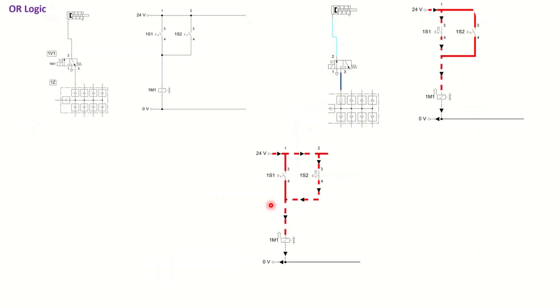The second important circuit I'm going to show is OR logic, and the question is how we design OR logic inside electro-pneumatic circuits. The answer is easy — we need to put two switches in parallel. When we put these two switches in parallel, if we turn on any of these switches the system can operate. For example, if I turn on 1S1, the current passes to 1M1, 1M1 is energized, and from there we would have the directional control valve shifted to its second position. If I turn on 1S2, the same thing happens.